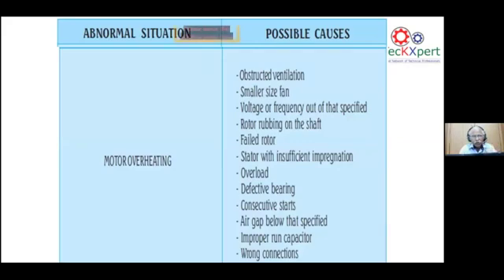The possible abnormal situations that come up in the motor and the possible causes. See, motor overheating happens. Having seen in the thermal imager that the motor is getting overheated, why? Obstructed ventilation. The ventilation should be there. I'll show in a few slides why obstructed ventilation causes the non-drive temperature to go more than the drive temperature, and the motor suffers more there.